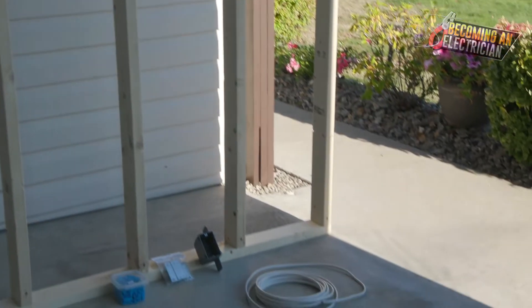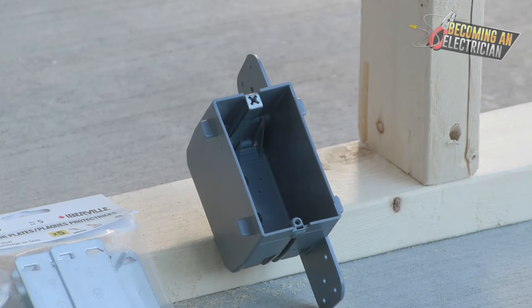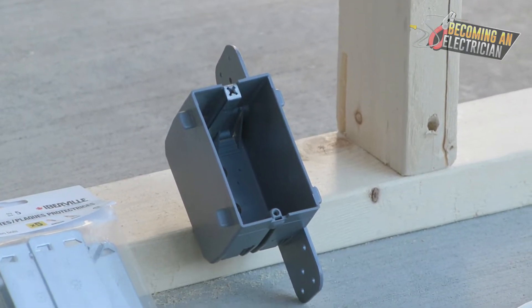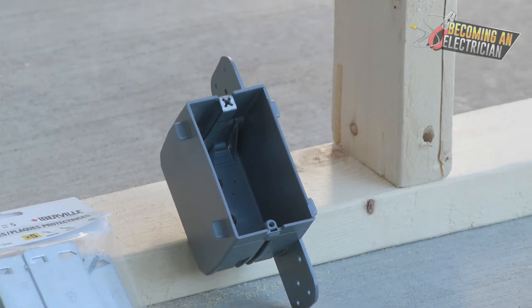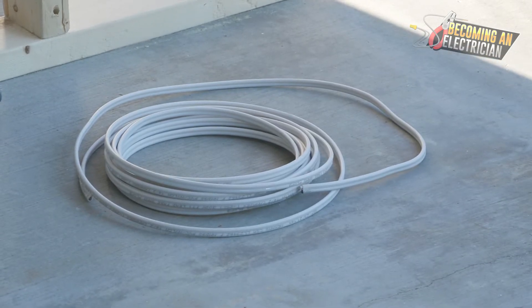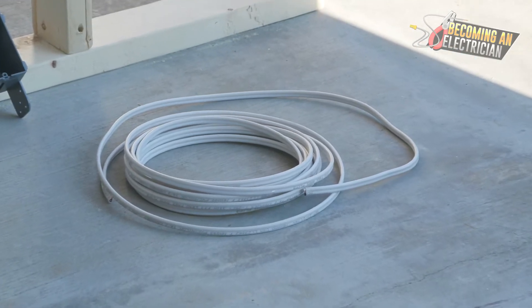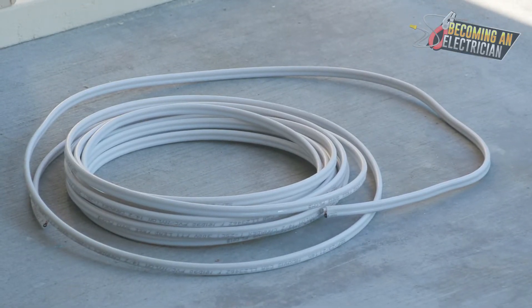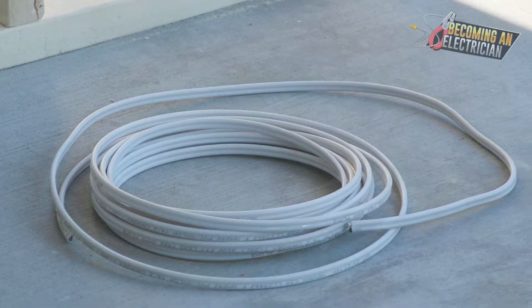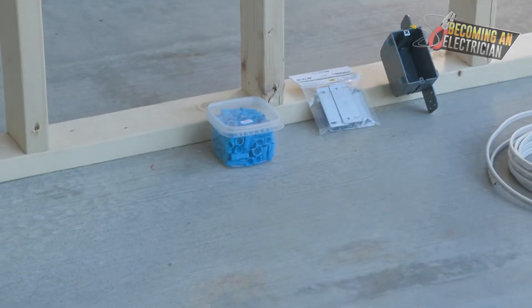The first thing we do in the rough-in stage is install our electrical boxes. This is a single gang box — there are also double gangs, triple gangs, and more. We also run electrical wire. This is the most common home wire: NMD, or Romex as you might hear it called. It's 14-2, meaning 14-gauge wire with two conductors. Right beside it you'll see wire nuts, which we also use in the rough-in stage.